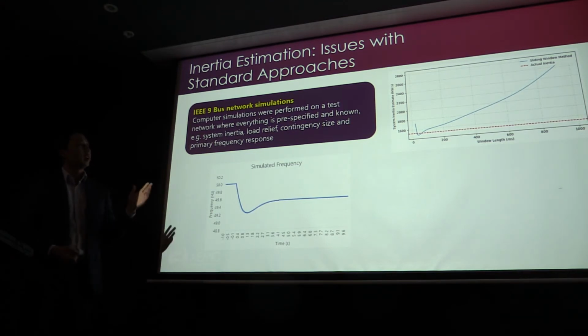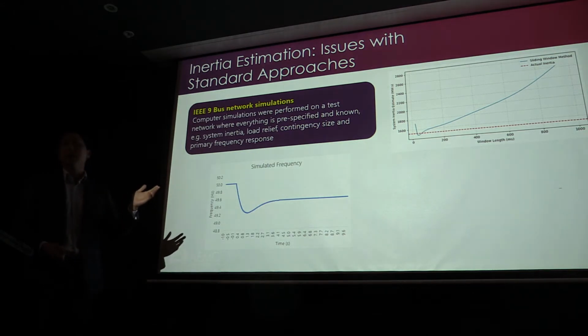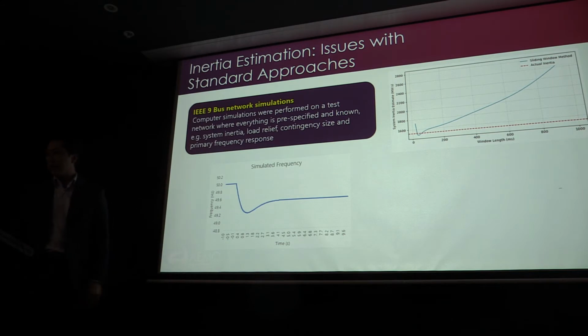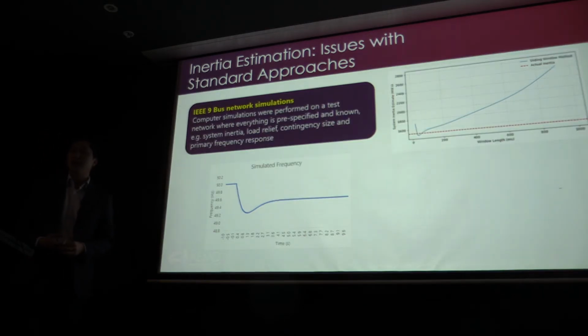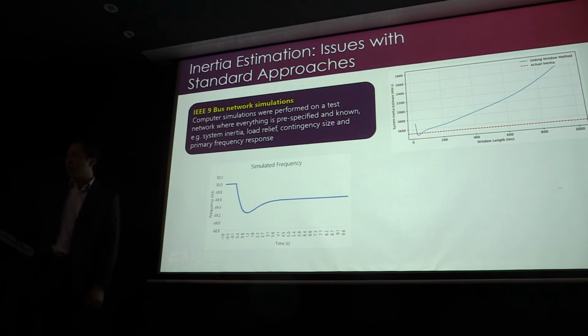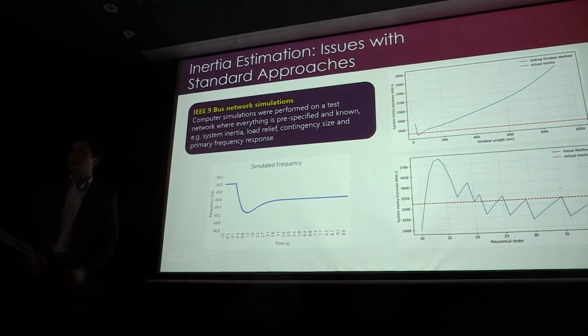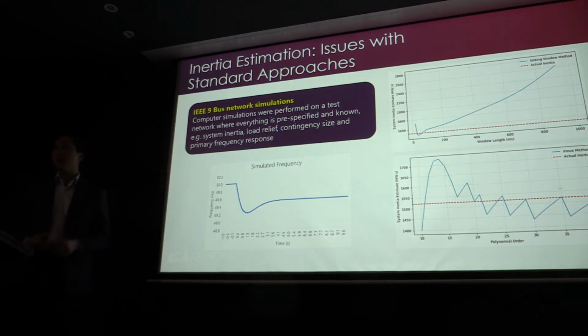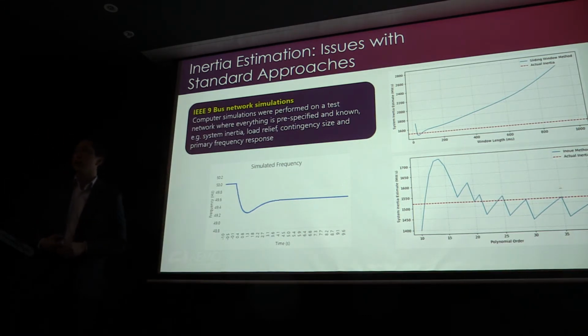Then you can see that as you increase your window length, your inertia estimate gets worse and worse. In fact, you overestimate it. You could overestimate it by almost a half or more. So if we use 500 milliseconds, you can see here that it's about 2,000 megawatt seconds, so we're more than 400, 500 megawatt seconds higher than our actual inertia. Excuse me, Joe, this is to measure the total system inertia? It is, yeah. Not just generator inertia? No, well, we know what that is. We're always looking at load inertia as well, yeah.